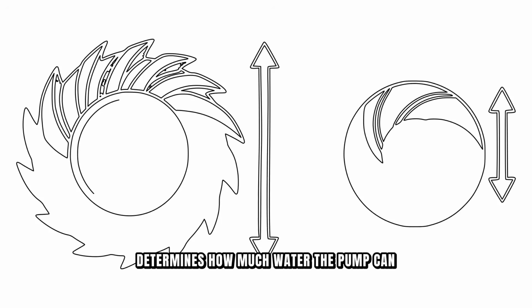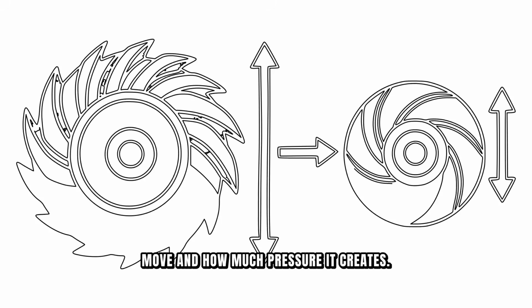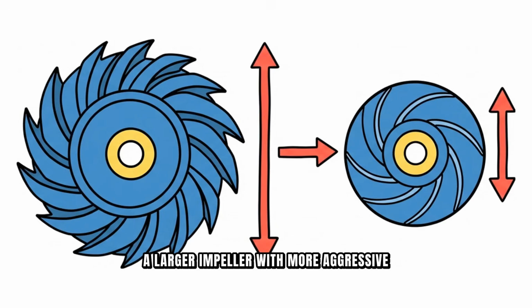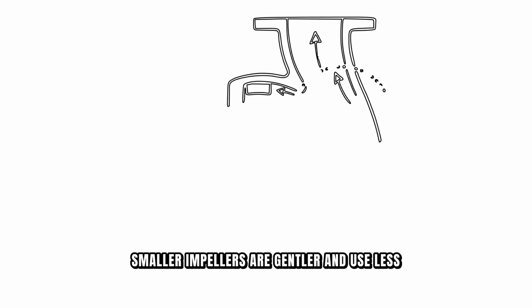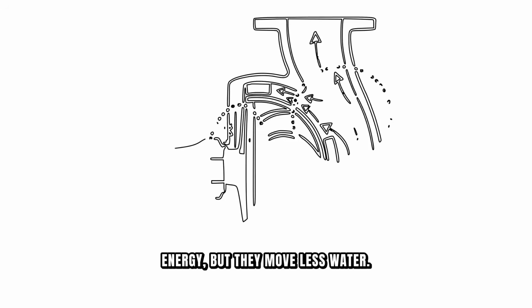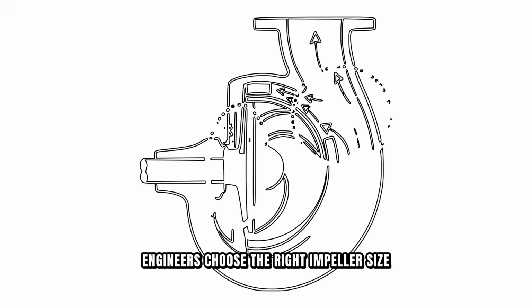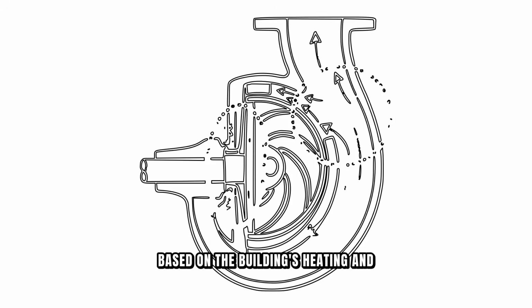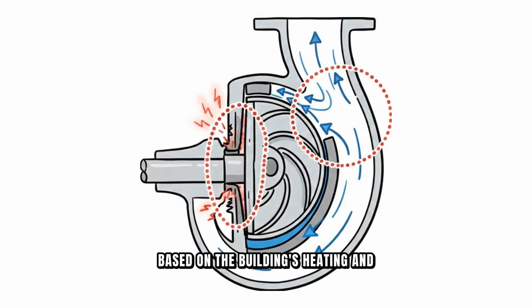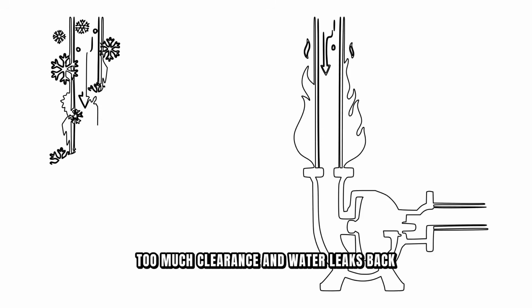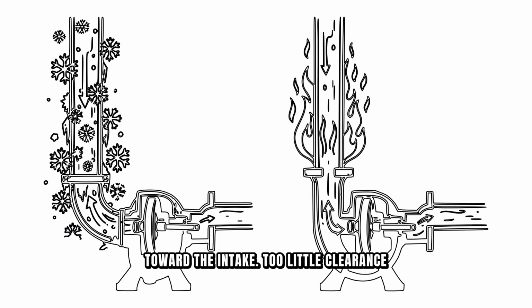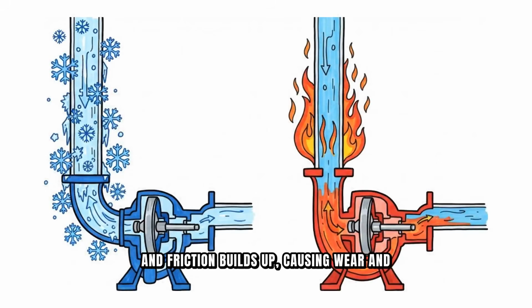The size and shape of the impeller determines how much water the pump can move and how much pressure it creates. A larger impeller with more aggressive blade angles will move more water faster, but also creates higher pressure. Smaller impellers are gentler and use less energy, but they move less water. Engineers choose the right impeller size based on the building's heating and cooling demands. The impeller also needs clearance inside the pump housing. Too much clearance, and water leaks back toward the intake. Too little clearance, and friction builds up, causing wear and heat.